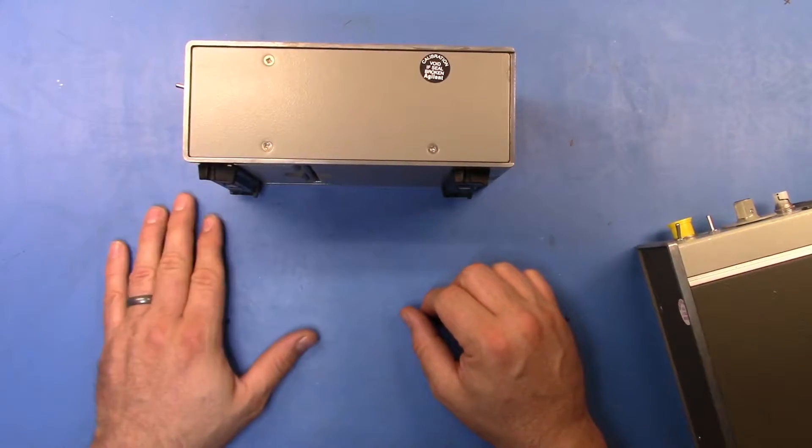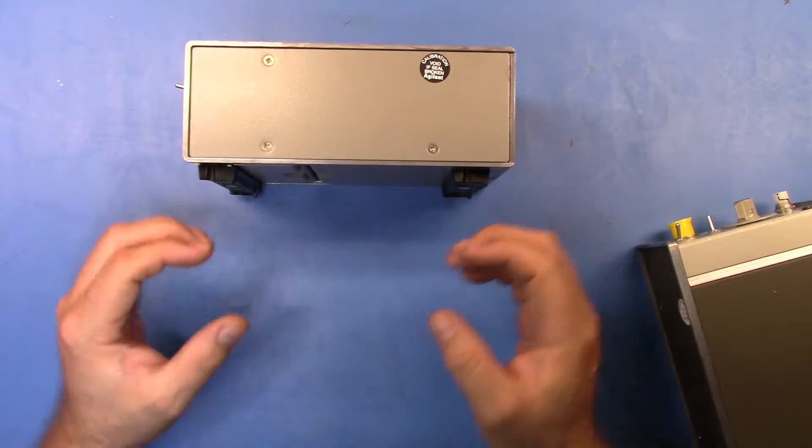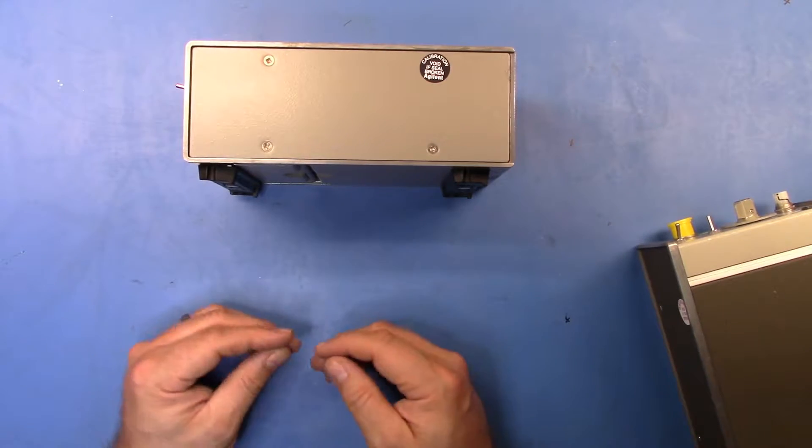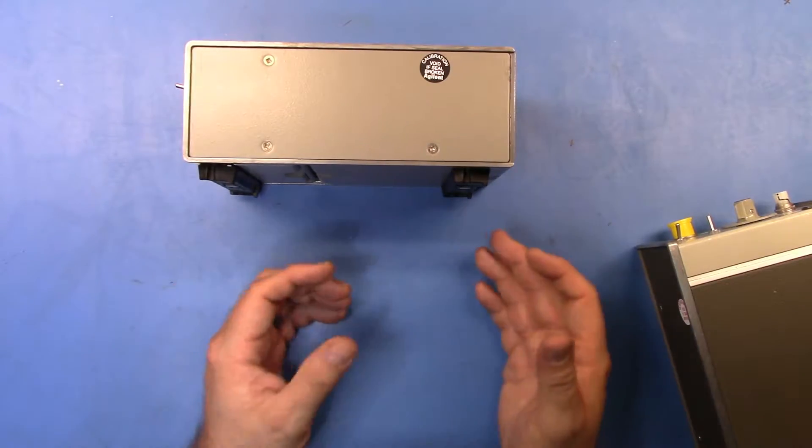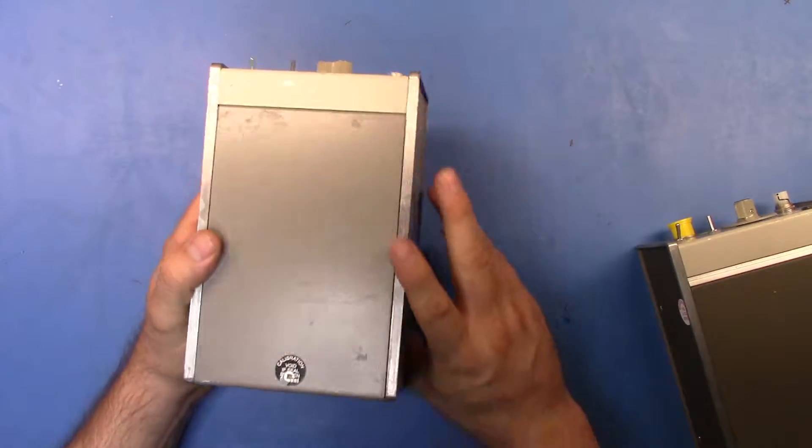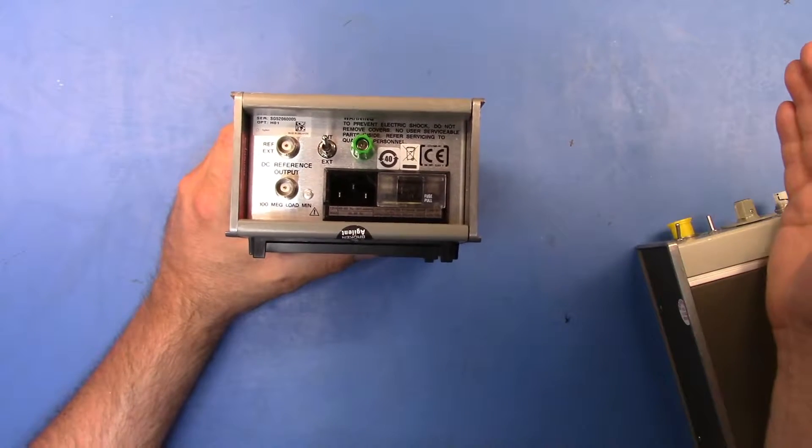That's great for calibrating the 435, 436, 437 meters. That's perfectly okay. When you start getting into the newer models, the EPM range, and in fact the meter that I bought just recently, which was the E4418B, that internal reference is no longer accurate enough.